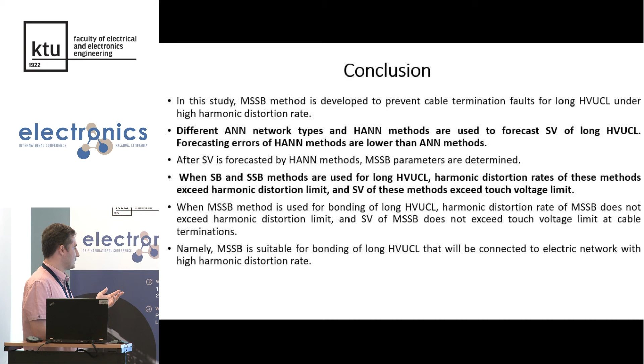Can you explain such a thing? Three phases are put in individual shields. Why not put all three phases into one shield? Because then you would get rid significantly of this sheath current. So what is the reason that each cable is separate?